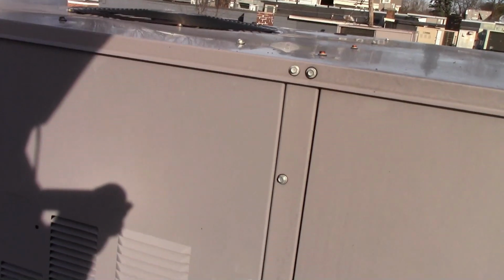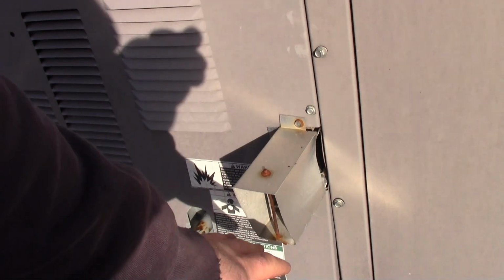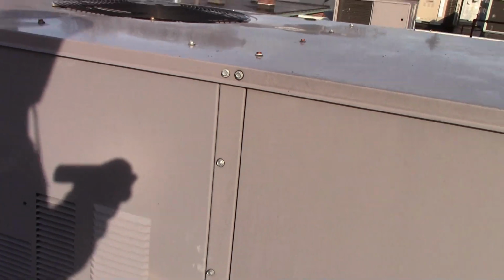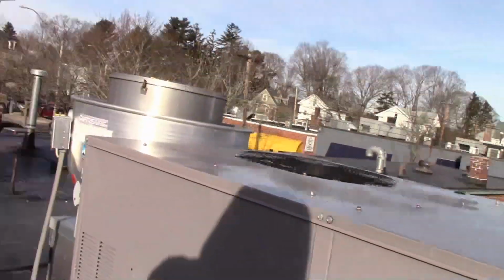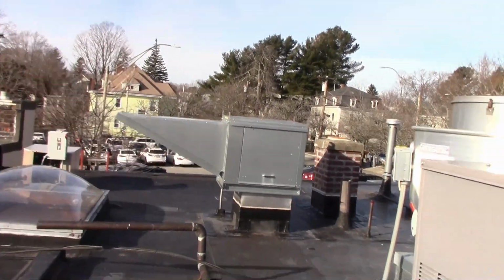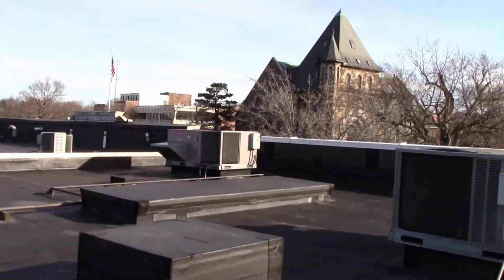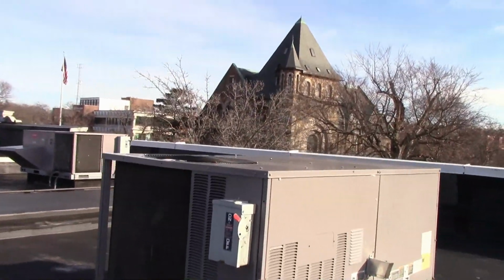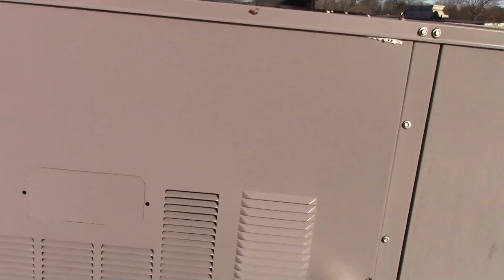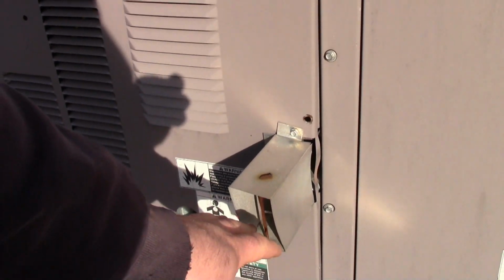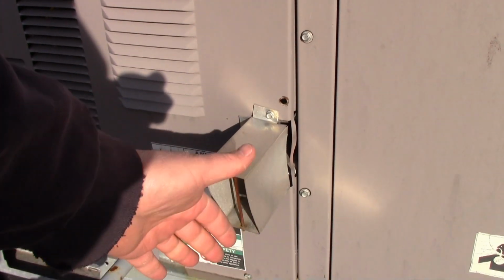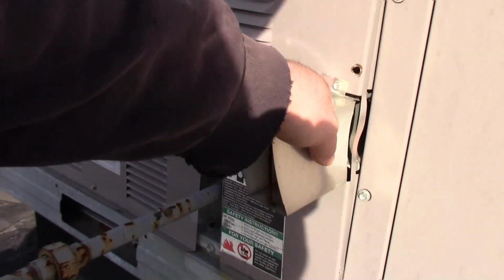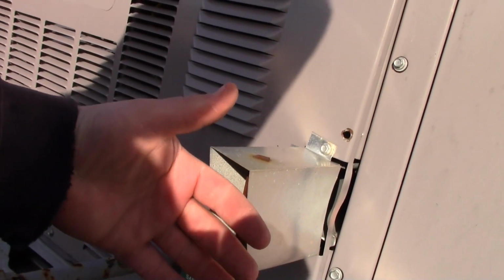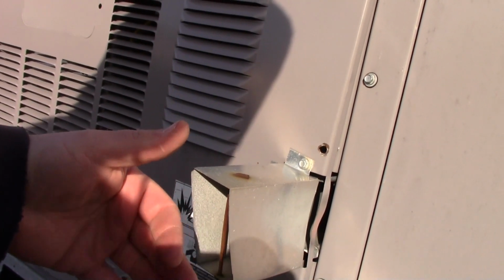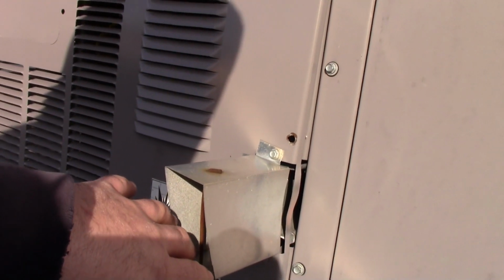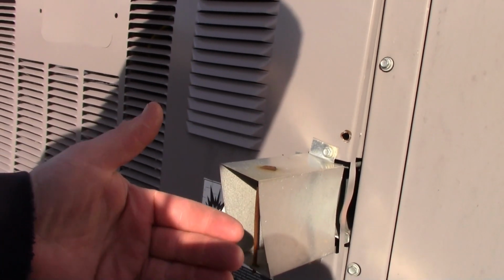So this is the kitchen unit, I'm assuming back of house. Alright, this one is running, so that's not our problem. The kitchen is probably cold from a combo of the front unit not running and that sucker dumping in ice cold air. This front one here, this is not running. Alright, so this air is cold. So that means, it's actually not as cold as outside, but that just might be sucking the warm air from the heat exchanger itself out. I don't think this one actually fired.